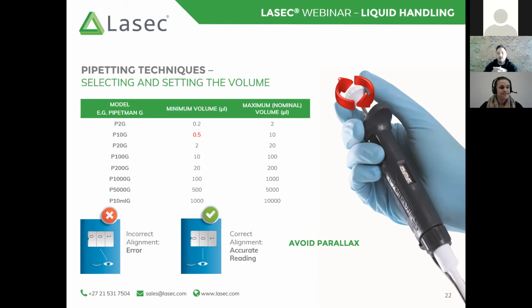We're now going to set that volume. Because of the way that the volume counters on the pipettes are structured, they are subject to an error called parallax. Parallax is essentially an error whereby you are looking at the display from a different angle and it will show a different reading. It's very similar to looking at a measuring cylinder that's not at eye level, for example. So it is extremely important that you face the pipette head on and make sure that it is at eye level and that you are looking at it directly. In some situations, they also recommend to improve this by rotating the pipette and holding it horizontally, looking at it straight on. All right, so that's going to be the first step, making sure that you are accurately setting the volume to the mark on the pipette.